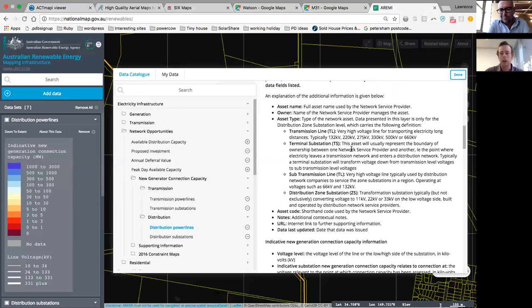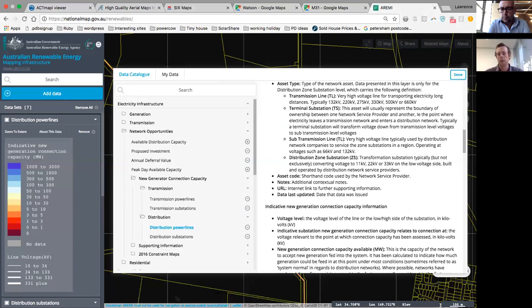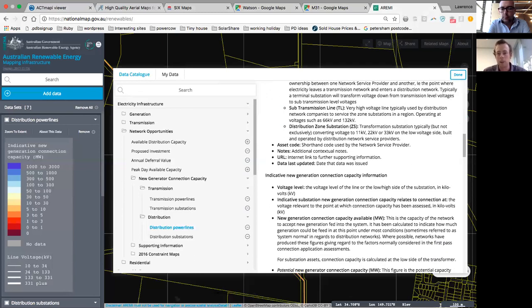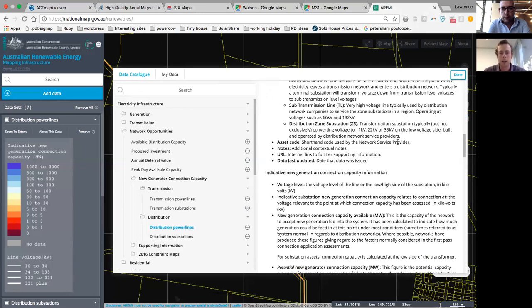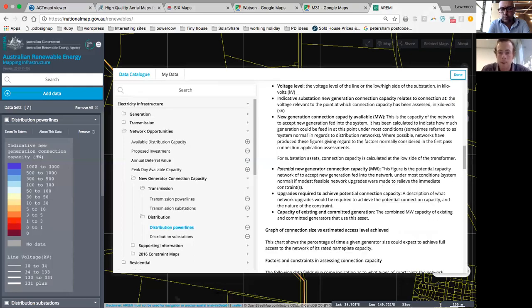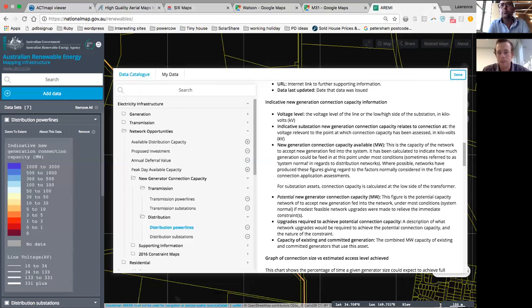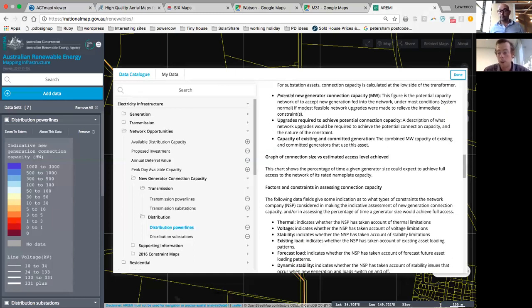A terminal substation is the boundary between a big transmission company and the smaller distribution companies, so it's not all that useful for someone developing anything lower than maybe a 20 megawatt plant. It helps you identify that it's the distribution substation and distribution lines that become most relevant to community energy proponents, along with descriptions of voltage, connection capacity, and how it's calculated in this particular network's area.